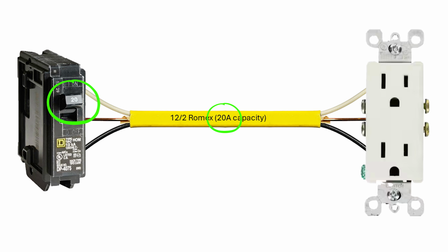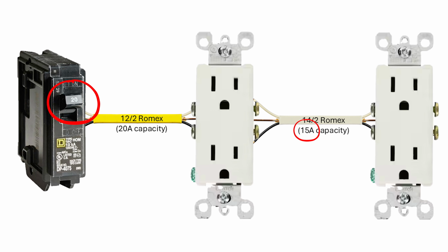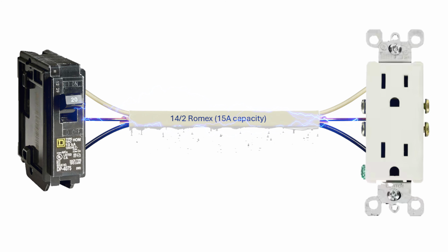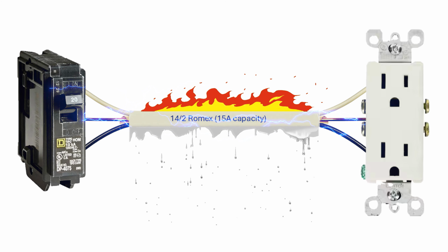One important thing to note: never install a cable that has a lower current rating than the breaker it's connected to. So this is okay, but this is not. Neither is this, even if you think the last outlet won't draw much current. This is because the breaker won't be able to protect that lower rated cable, and it could get hot, melt, and potentially cause a fire. So just don't do it.